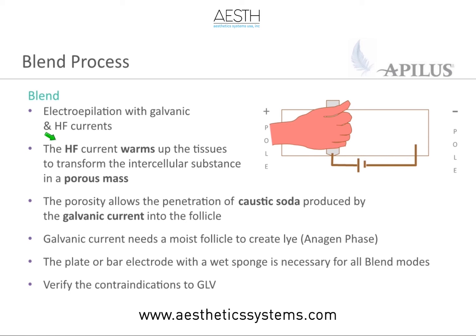What happens with the blend method is that we are using the galvanic to create lye, and lye is corrosive. It destroys tissues. So we create the lye in order to dissolve the hair follicle. High frequency in this case is just there to facilitate the lye production, not to actually coagulate. We want to be careful not to increase the high frequency so high that it is counterintuitive to the galvanic method. So we keep it down low so that you are just increasing the conductivity of the galvanic itself. It actually helps with the caustic soda and the galvanic current in the follicle.